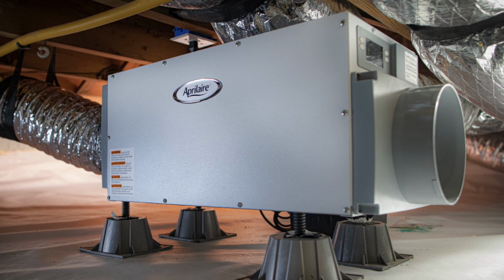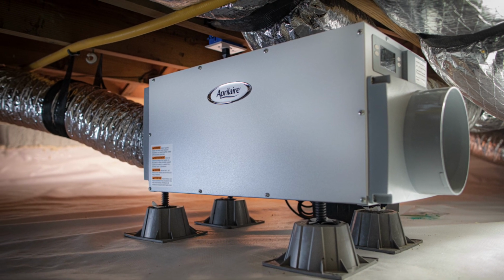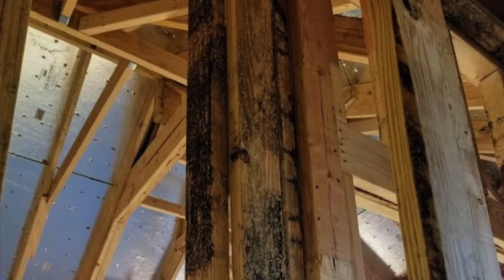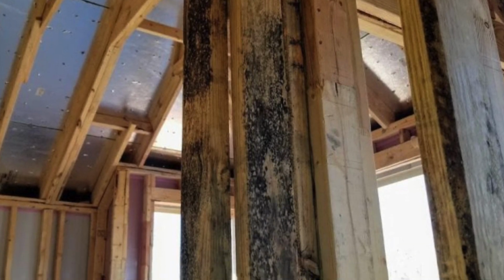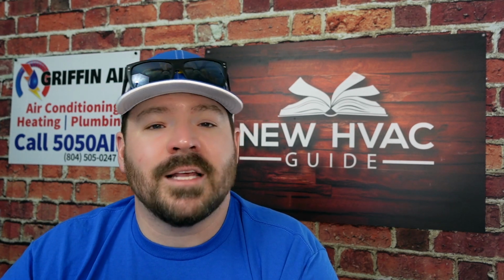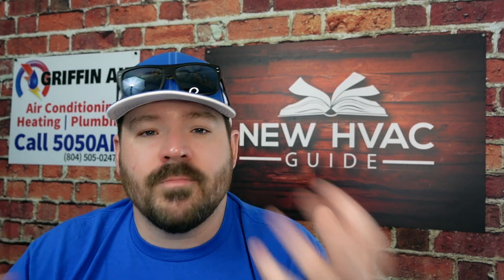But getting back to housing, when you have a really tight home and the system isn't removing enough humidity, folks have to account for that by installing dehumidification and things like that. That ties back to the short cycling issue - it's less comfortable in the house, but it also creates an environment where mold can grow, if there's high humidity and somewhere for it to grow, with humidity, something to feed on, and the right temperature.